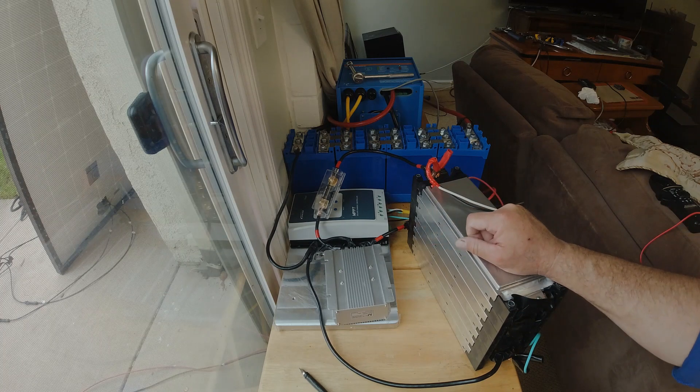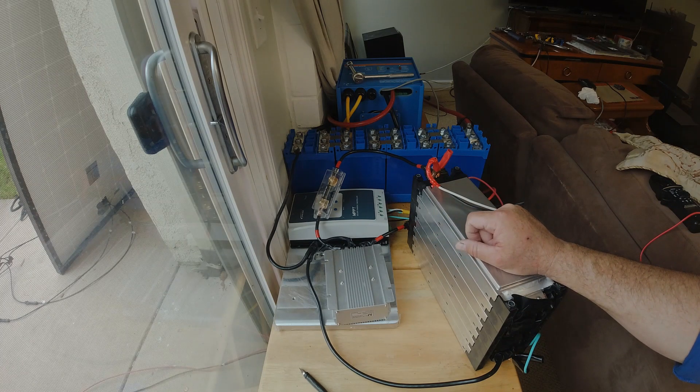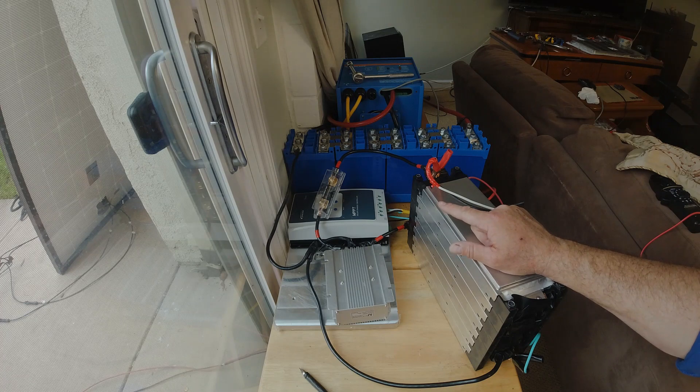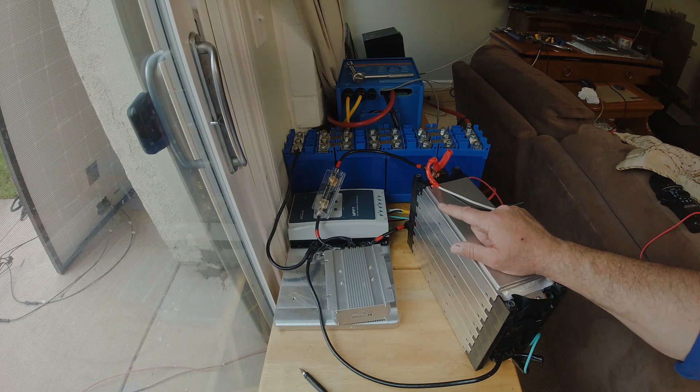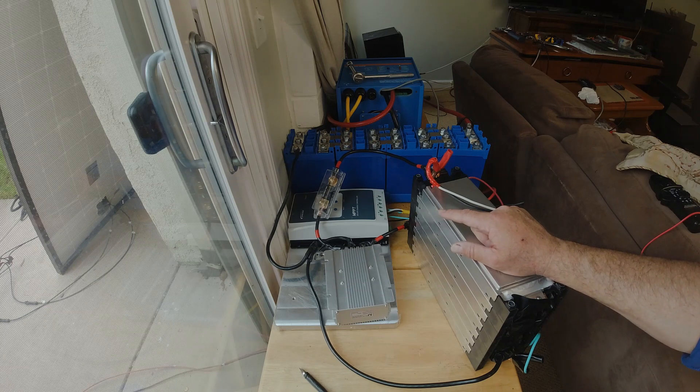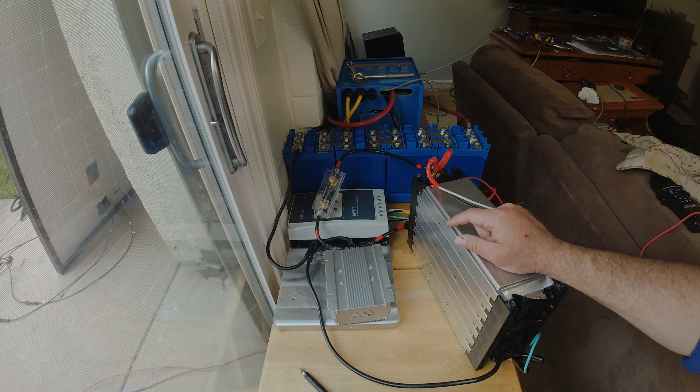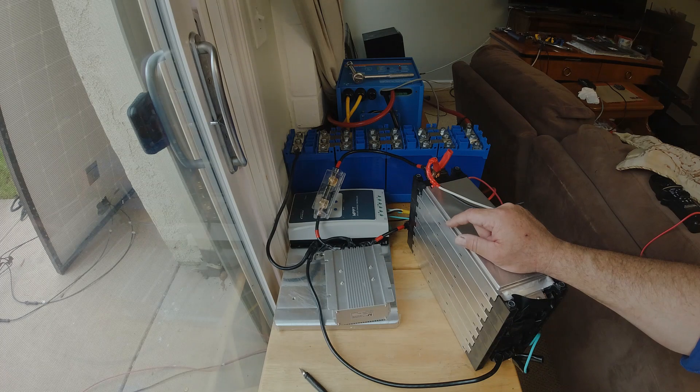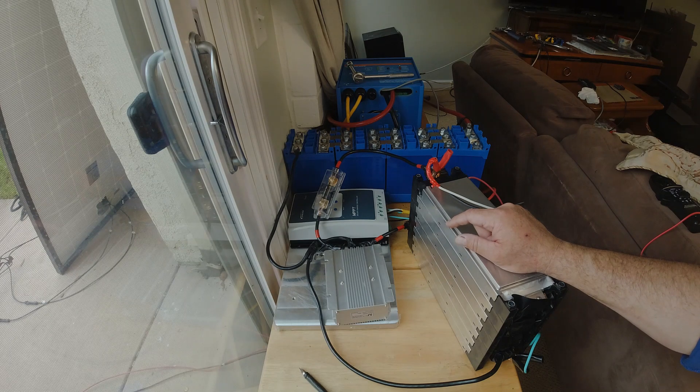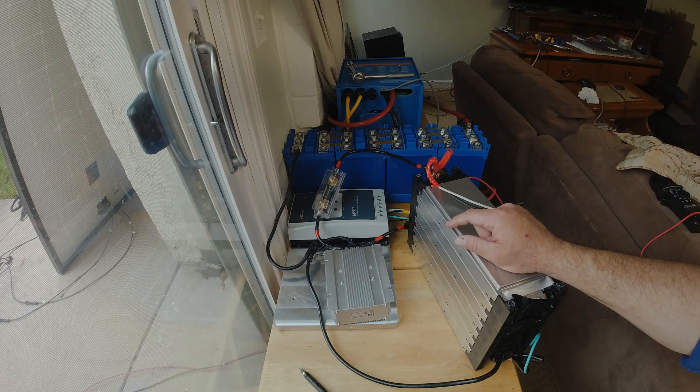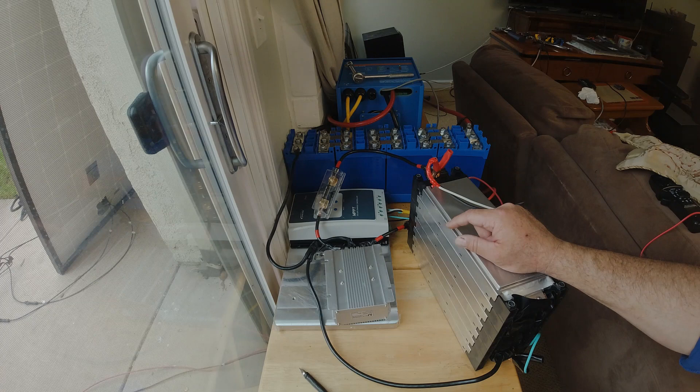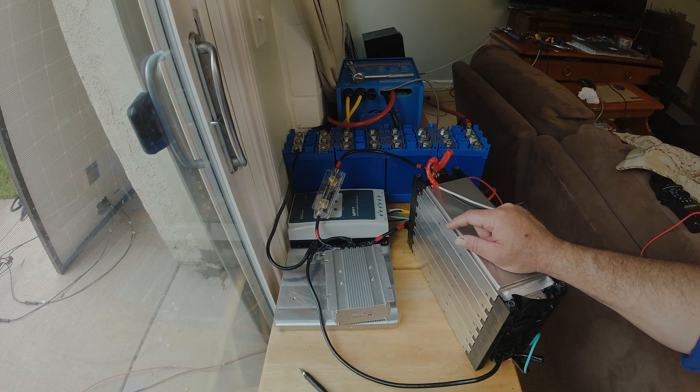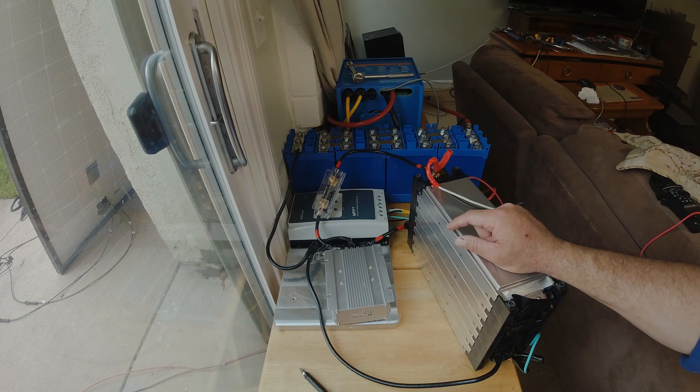That is programmable but it's a complete pain to program. I actually have a Victron coming, the 150/50, which is 150 volt max which can't be exceeded, and then 50 amp output max which can be exceeded. You can have more amps on your system, over-paneling they call that, which is fine. The charge controller will only put out 50, so if you're pushing 3000 watts and you have a 50 amp charge controller, you're just not going to get all the power at peak sun.